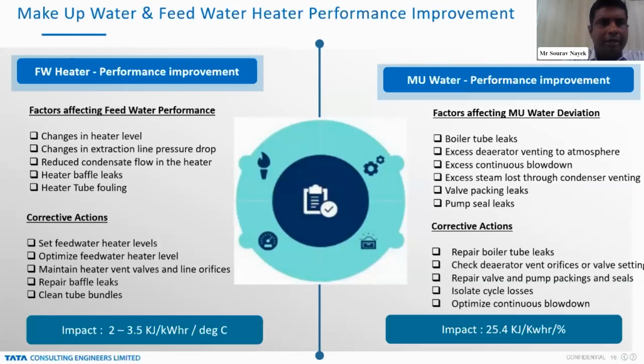Next point is feed water heater performance improvement and makeup water. Maintain the proper percentage of makeup water quantity, so that there is not much deviation from the design value. The feed water heater configuration, the number of feed water heaters giving the regenerative effect into the TG cycle, is very important. And when we are selecting the feed water heater, the TTD and DCA selection is also important, which will be a significant factor for improving our heat rate. As we lower the TTD and DCA, the heat rate will be improved.